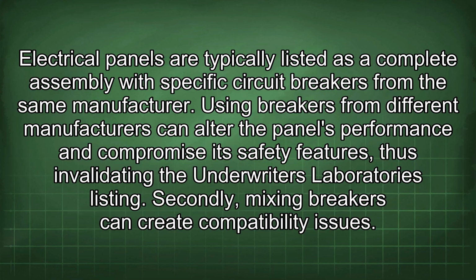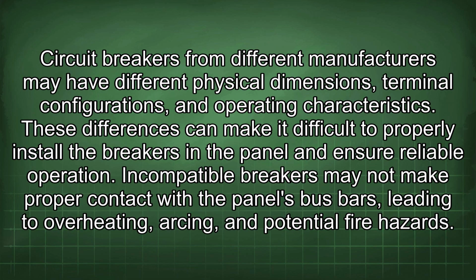Using breakers from different manufacturers can alter the panel's performance and compromise its safety features, thus invalidating the underwriter's laboratory listing. Mixing breakers can also create compatibility issues, since circuit breakers from different manufacturers may have different physical dimensions, terminal configurations, and operating characteristics. These differences can make it difficult to properly install the breakers and ensure reliable operation.